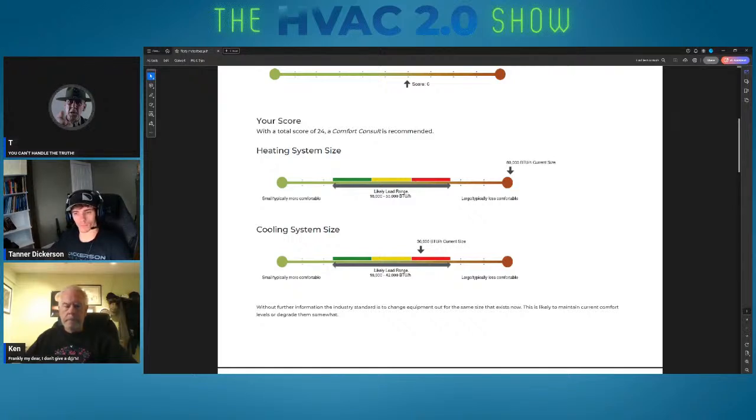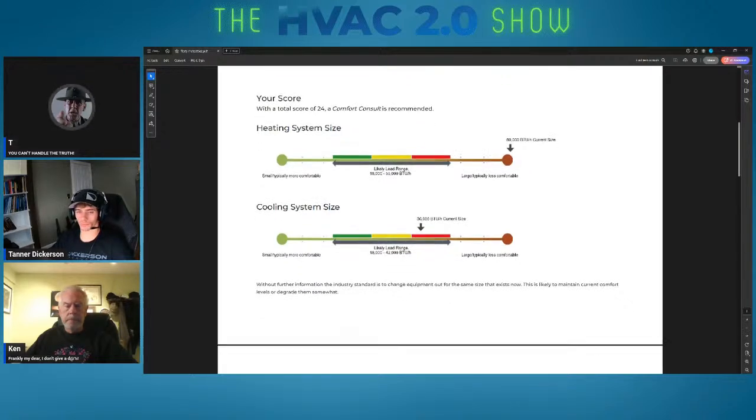And then the next step is the importance of sizing, which is going to tie to the 6 functions. A lot of the 6 functions require load matching and continuous mixing, for example, and you can't get those things if you grossly oversize, because you're going to get short cycling.